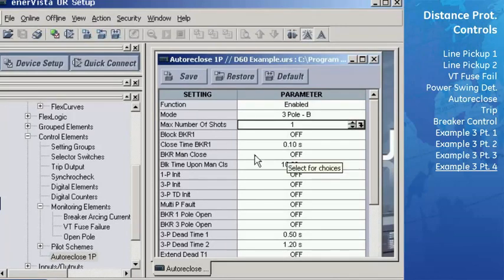left as is. The breaker manual close can be left as off, since the manual closing is done in the breaker control function. The block time upon manual close can also be left as 10 seconds. This means the auto recloser will be blocked for 10 seconds after a manual close. The recloser is initiated from the trip output function, so no assignment is needed for 3-pole initiation. Since we are only using one recloser shot and the breaker status will be read by the breaker control function, the next few settings won't be needed.